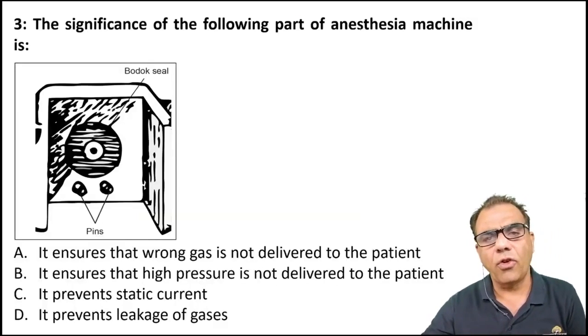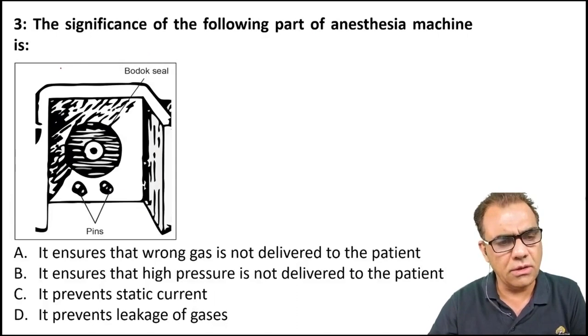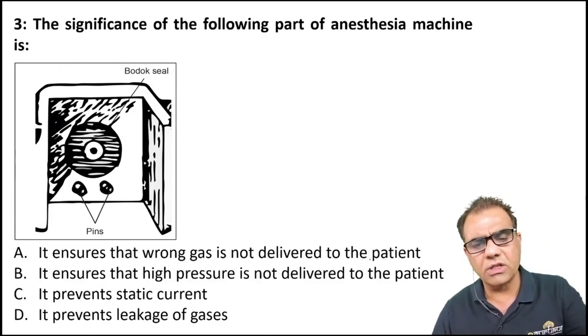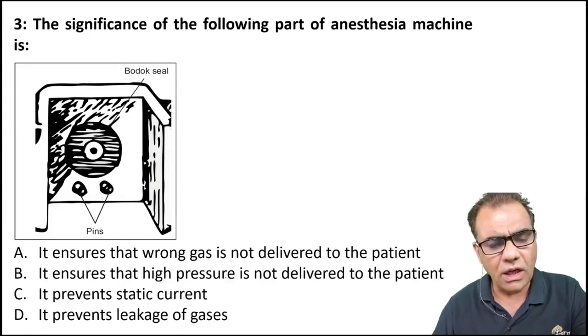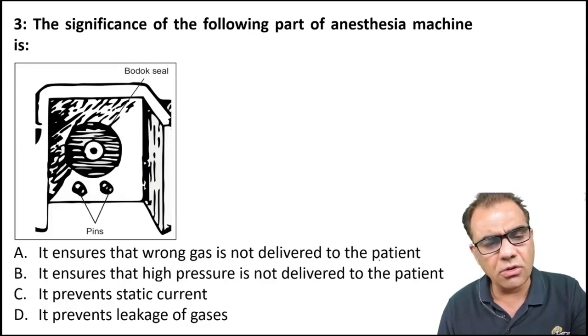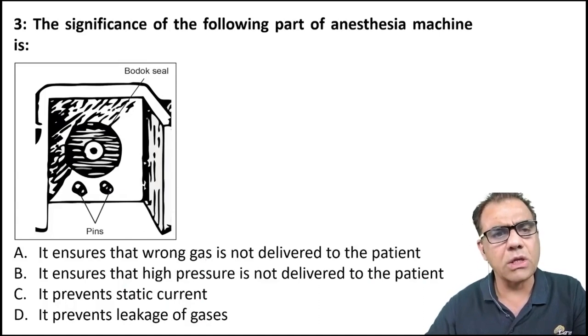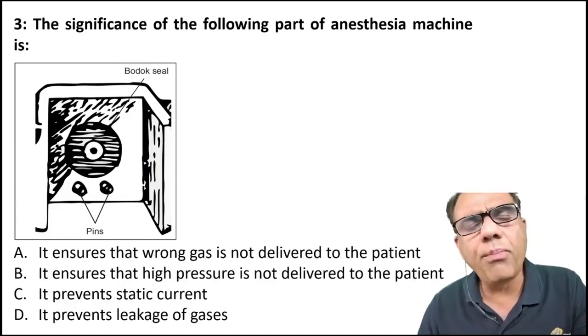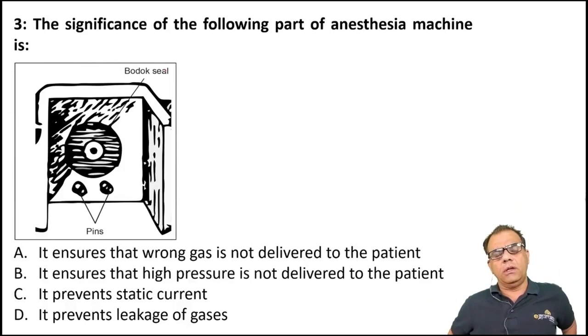The significance of the following part of the anesthesia machine is that it ensures that the wrong gas is not delivered to the patient. It ensures that high pressure is not delivered to the patient. It prevents static current. It prevents leakage of the gases. Now what is this? Another very important thing about cylinders that you should know is the pin index system.